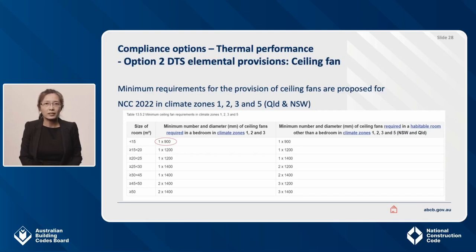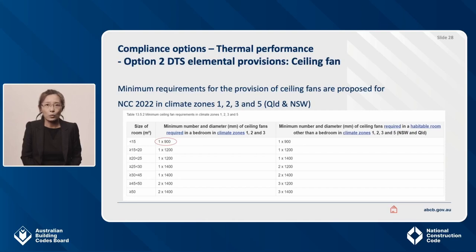Ceiling fans facilitate a significant reduction in the use of artificial cooling. The ceiling fan requirements have replaced the NCC 2019 requirements for air movement. In climate zones 1, 2, and 3, these requirements include both daytime and nighttime occupied spaces. In climate zone 5 — Queensland and New South Wales — ceiling fans are only required in daytime occupied spaces. Ceiling fans are not required in circulation spaces like hallways and entrance foyers. In climate zones 1, 2, and 3, a bedroom with an area less than 15 square metres requires a 900-millimetre ceiling fan.